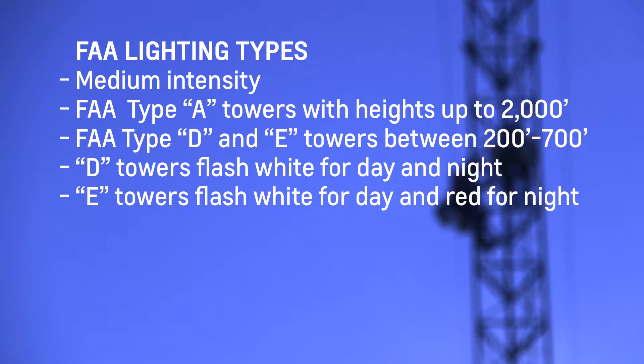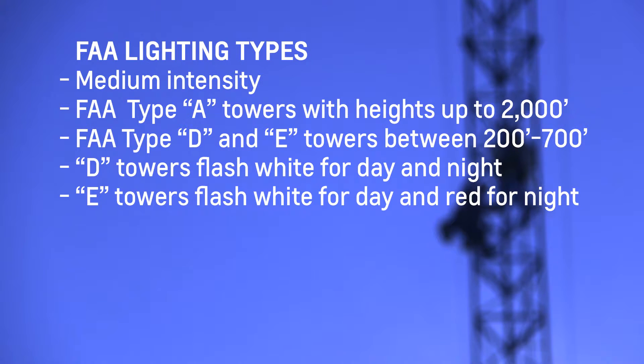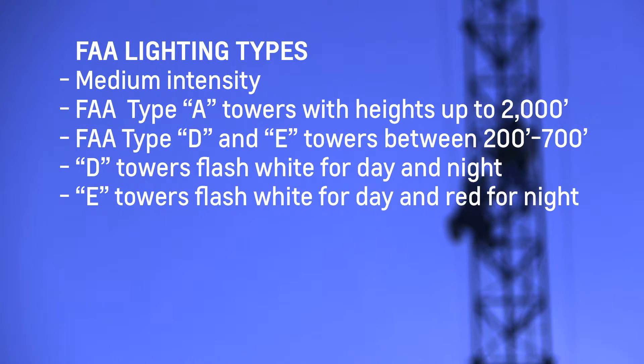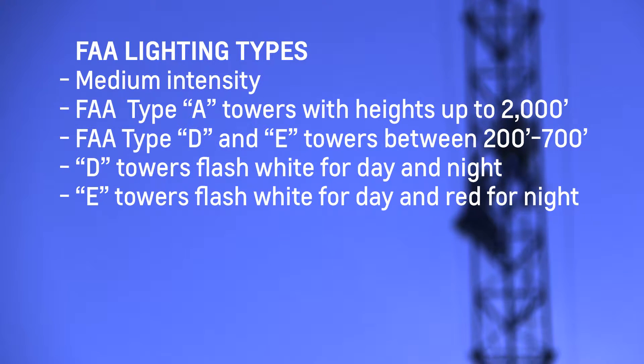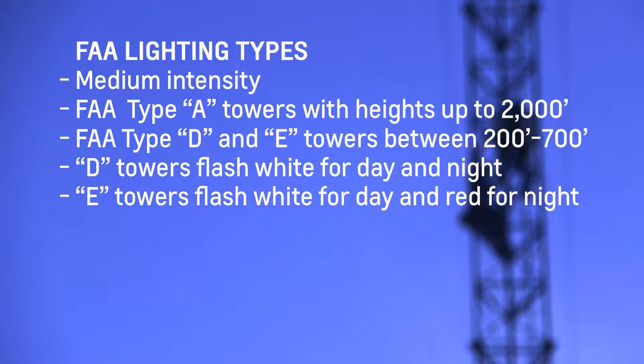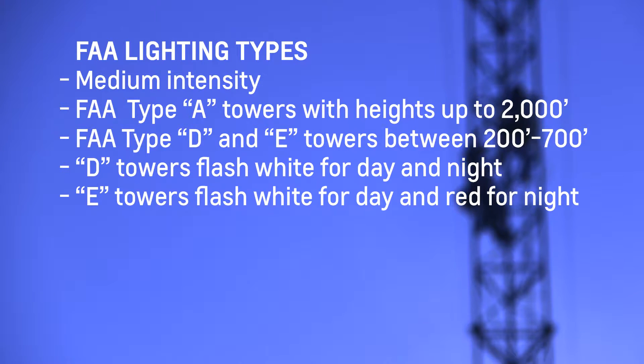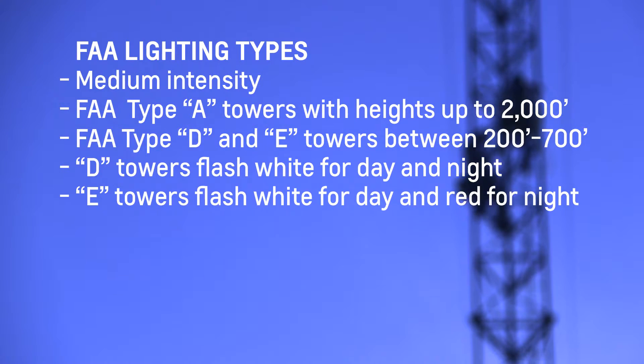Typically, towers under 200 feet do not require lighting. However, if the tower is located within three nautical miles of an airport, it is likely the FAA will require lighting.